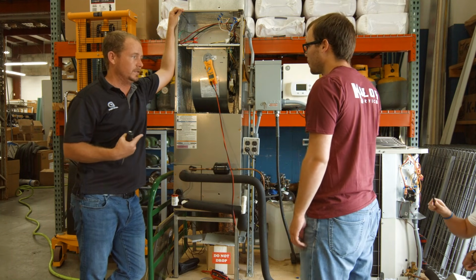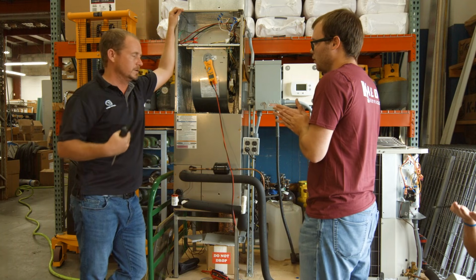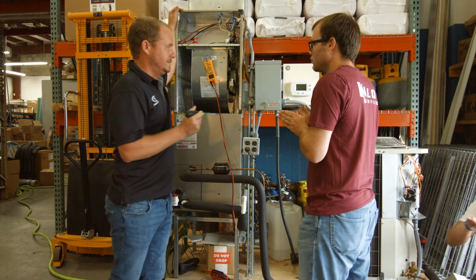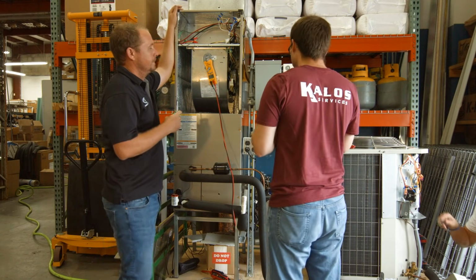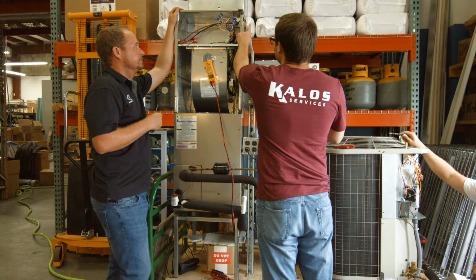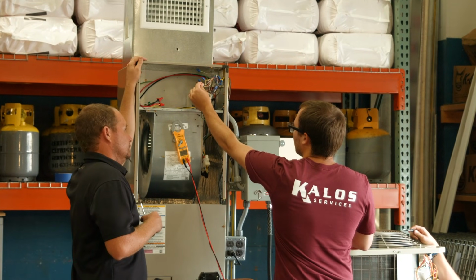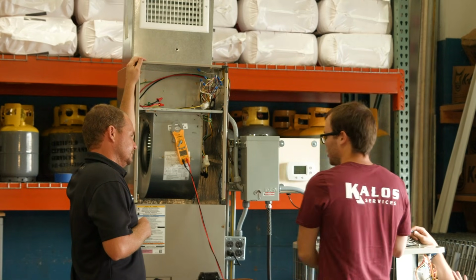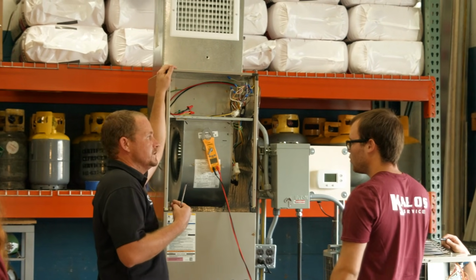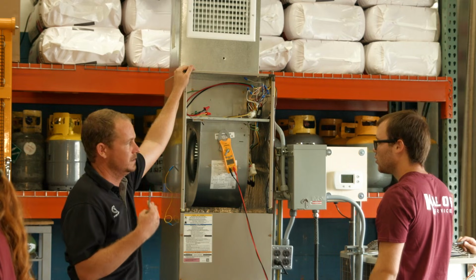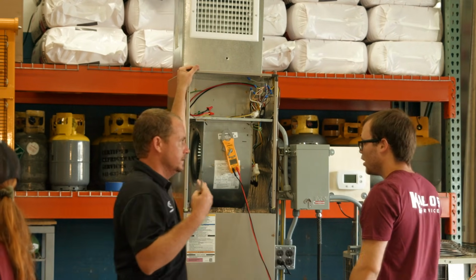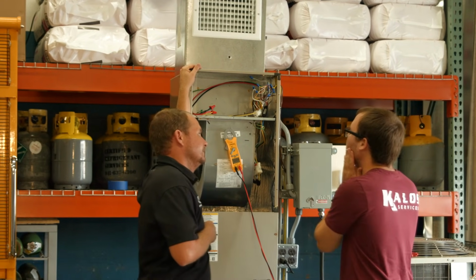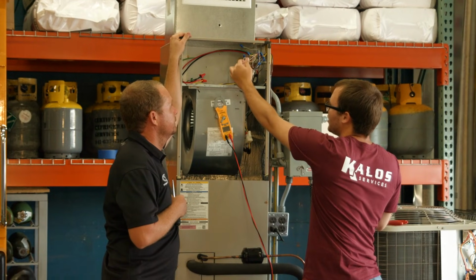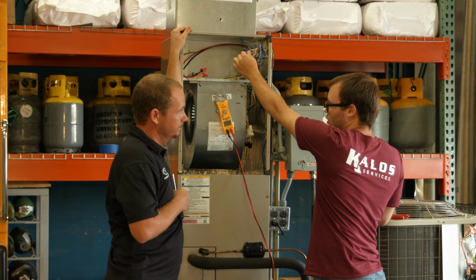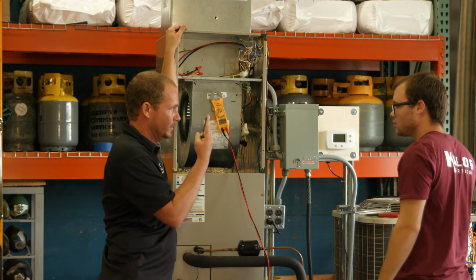Thermostat, right. What terminal on the thermostat? The O terminal on the thermostat, right? But what route does it take? It just goes from thermostat to air handler to this connection. Right. It goes through and goes to the condenser. Exactly. And so what are some things that could cause this? Let's think through that first. One common one that I've seen would be these weren't properly stripped back, so it's getting an inconsistent connection. Right. So a poor connection in between your O.